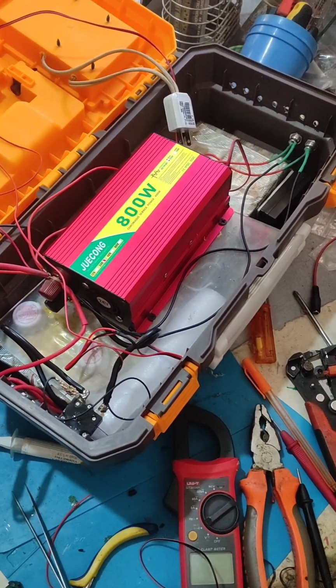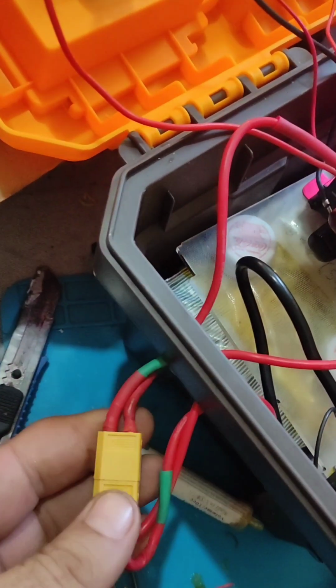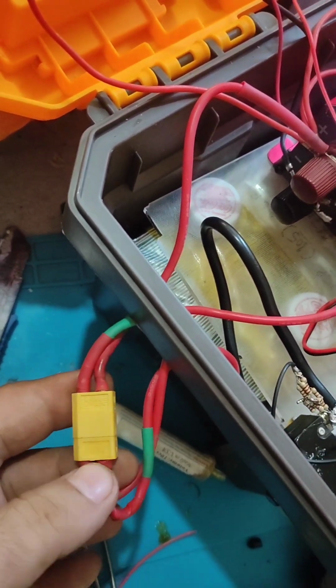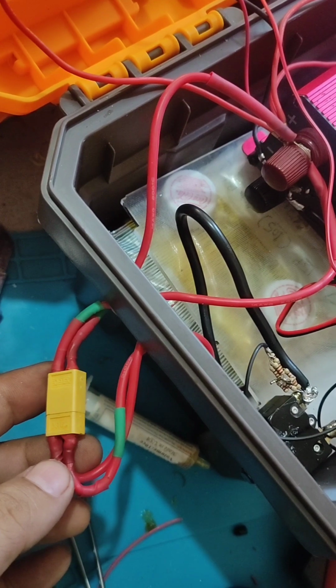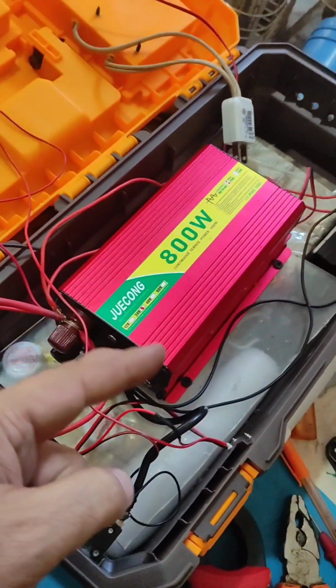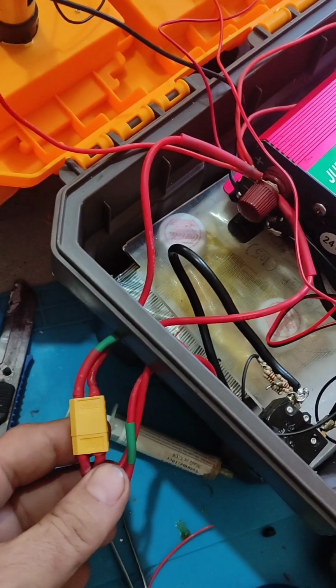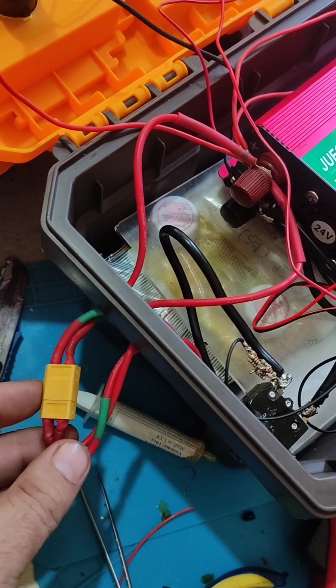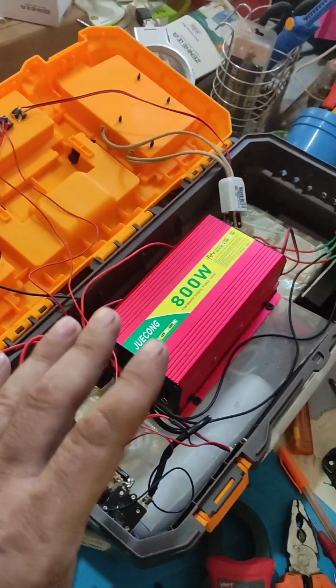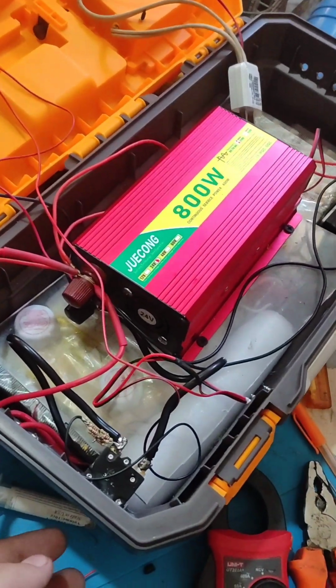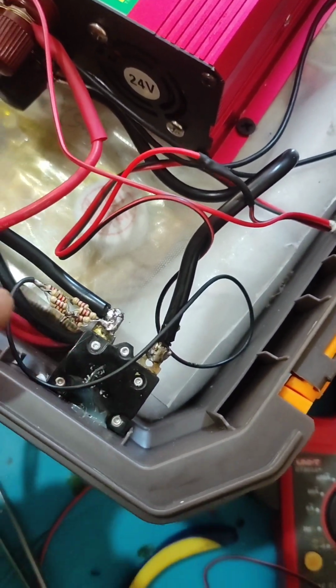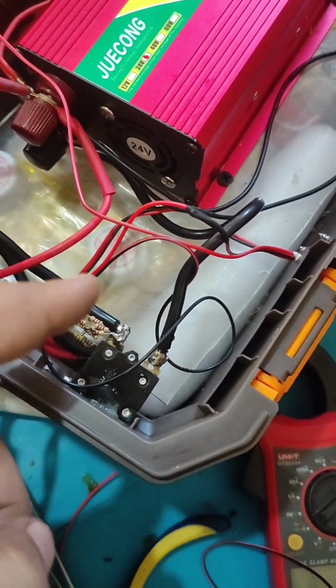Everything is complete. I install the positive disconnect as a circuit breaker outside, so sometime if the BMS has troubleshooting, we need to disconnect the load, so the positive can be externally disconnected without opening up the entire system. And here is the safety breaker on the ground.